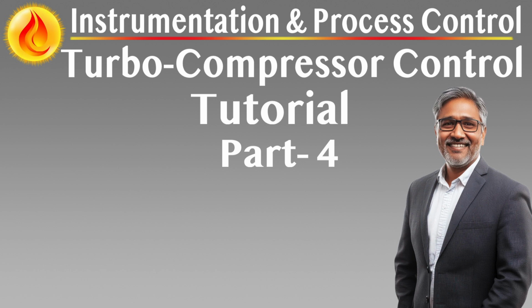Installation quality. Tubing and mounting hardware for pressure, temperature, and flow instruments must meet leak-free operation under full load, ease of removal and reinstallation, clear labeling, and tag plate visibility. Diagnostic support. Smart instruments support remote diagnostics from the HMI, auto-identification and configuration, and fault alerts in case of signal drift, loss, or calibration deviation.